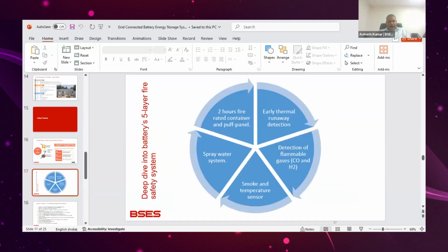So in this system there are 5 layers of fire protection. The first layer is early thermal runaway detection; 15 minutes prior to thermal runaway, we are able to detect it and act upon it. Second, 2 types of gas detectors are installed, CO and H2 gas detectors, and the ventilation system will be activated when LEL is more than 25%. Then smoke and temperature sensors are installed, and if they pick up, the aerosol fire extinguishing system will be operated. Then there is a cooling system as well as a water spray system.